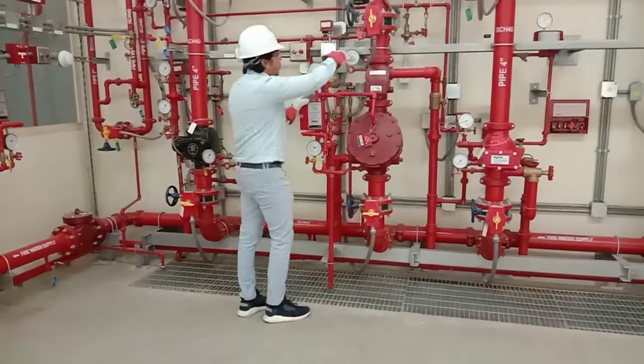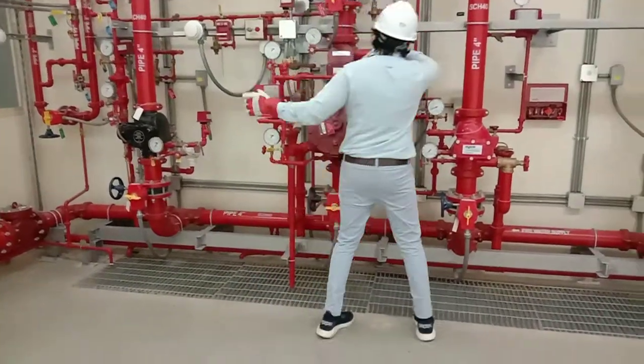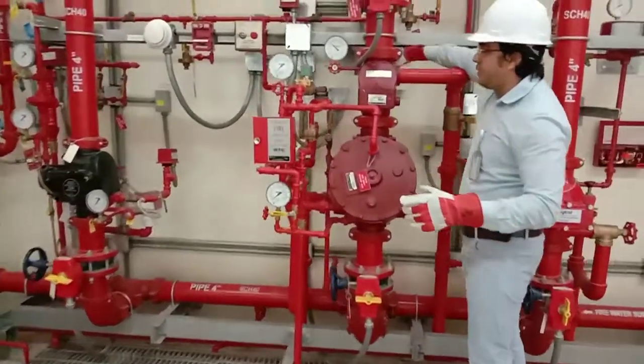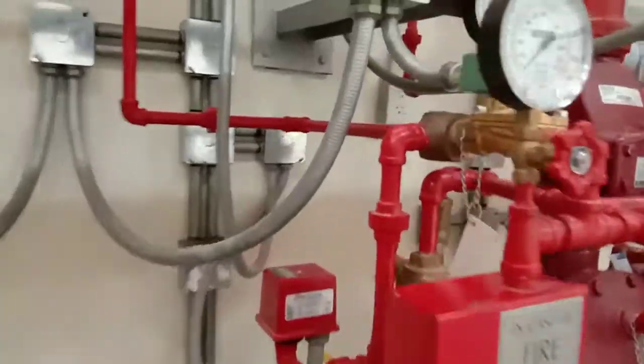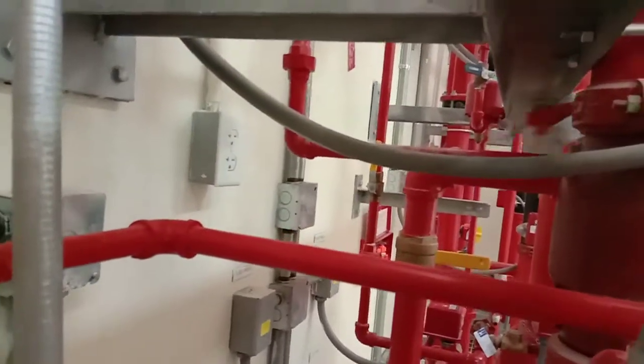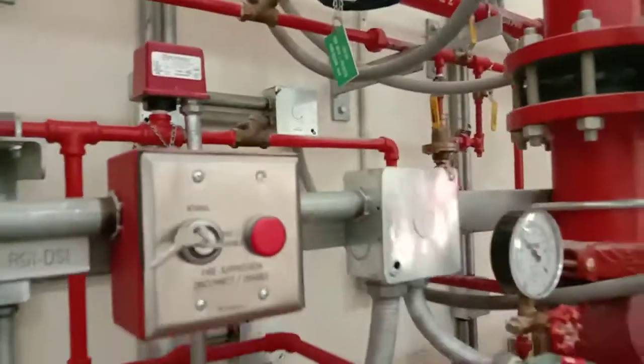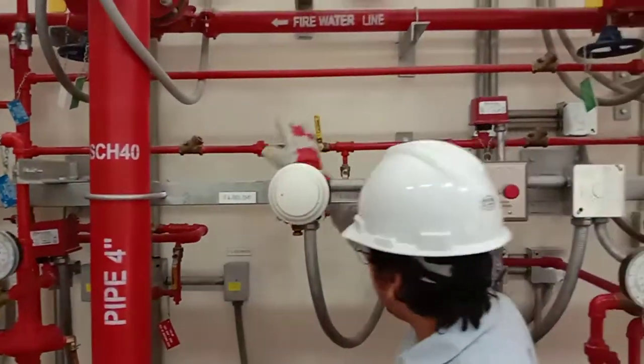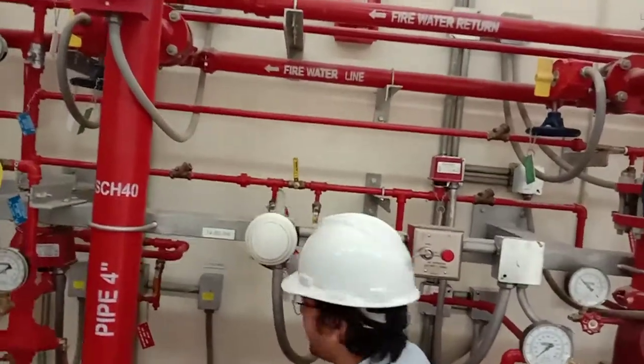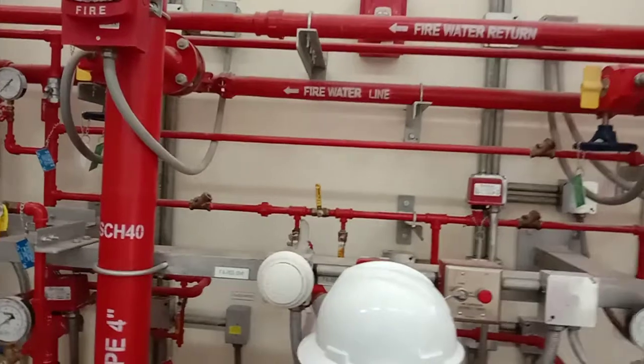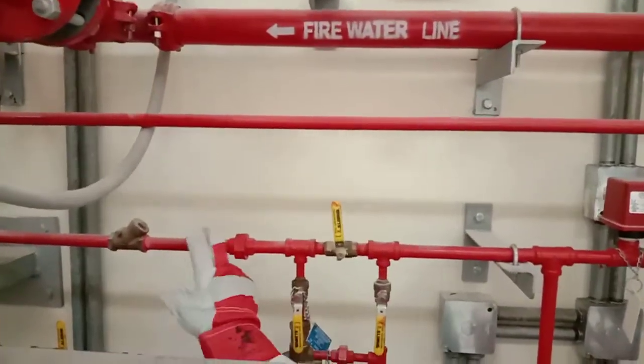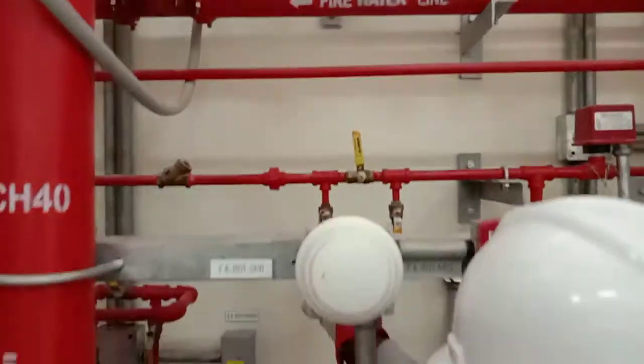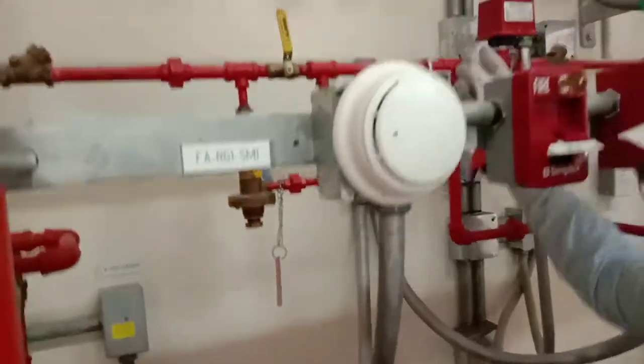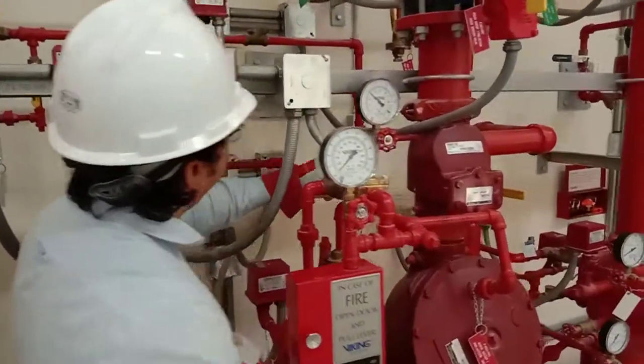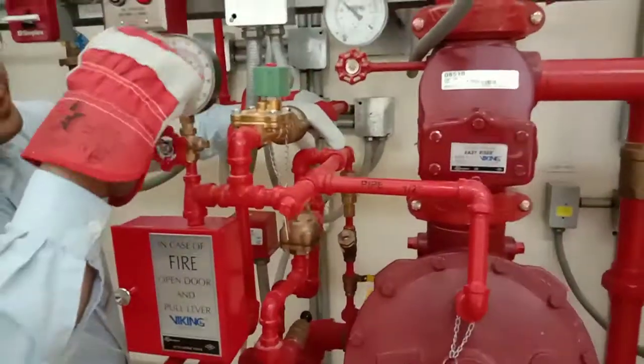So again, from the top side we have air, right? The air is coming from the back line. If you can see, this is the air line. From the top, the air line is coming from the check valve and trying to close those valves from this side, and the air is coming from the air maintenance device. This air maintenance device is similar to the one we saw in the dry pipe system or deluge system. The air will come from this side. We have a regulator. It will regulate the pressure and remove any kind of material from it. All the way from this, it will come to this side, right? We have an air connection here, and here we can see.